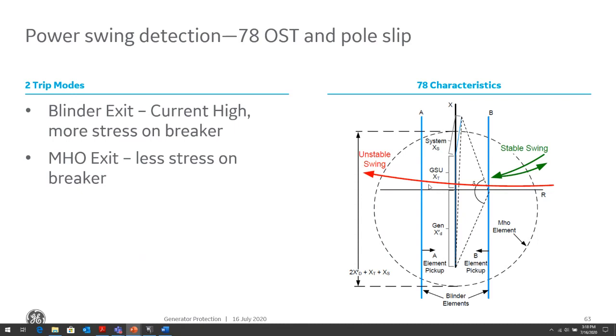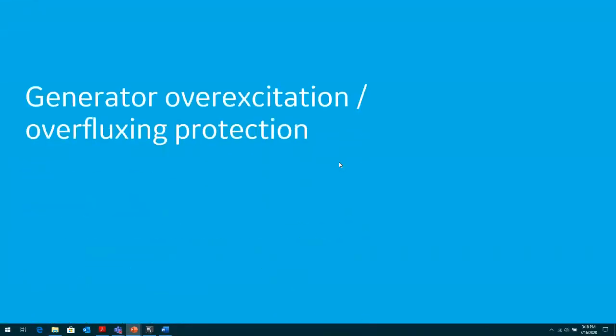So if we don't want too much stress on the breaker, we can wait until the power swing gets to the exit of the Mho circle. In that case, the power swing is further away from the generator, the currents are lower, and we have less stress on the breaker.